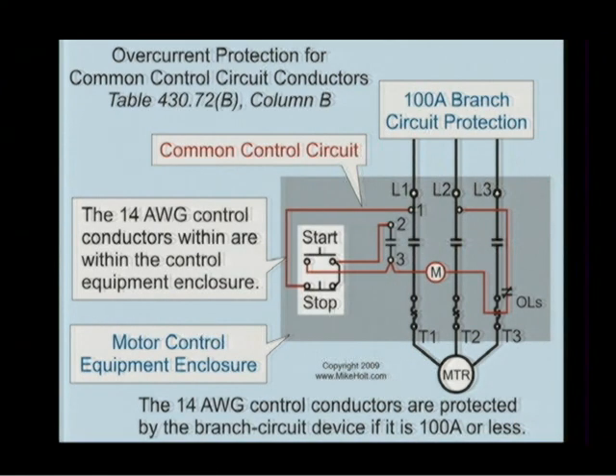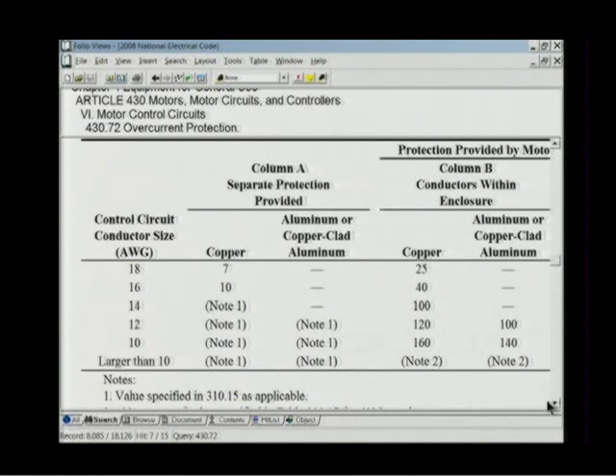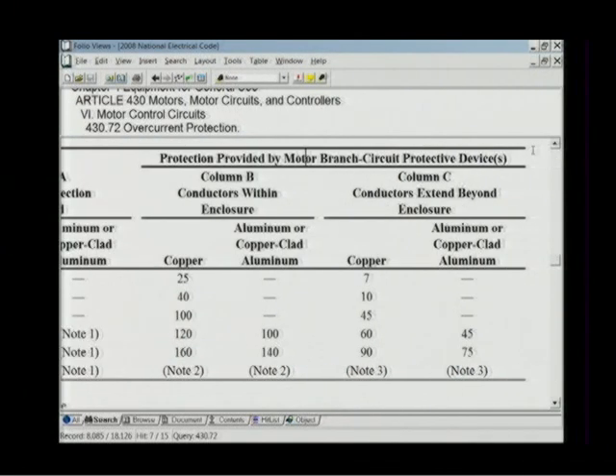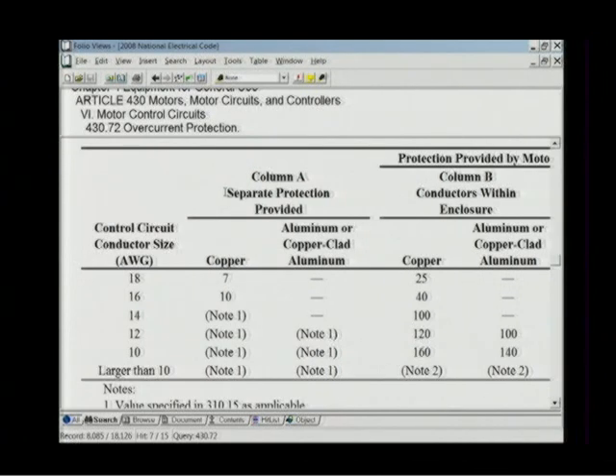All right, let's take a look at this example. This is already pre-wired. Line 2 picks up one side of the coil, and then we pick off Line 1 with a 3-wire control circuit in this example. This one has no overcurrent protection. If we go to table 430.72(B), column B, let's go to the code. Now we have to move over to column B. Column B says provided by the motor branch circuit protection. We can't see the wire size, so I'm going to have to go back over here. But column B is conductors within the enclosure.